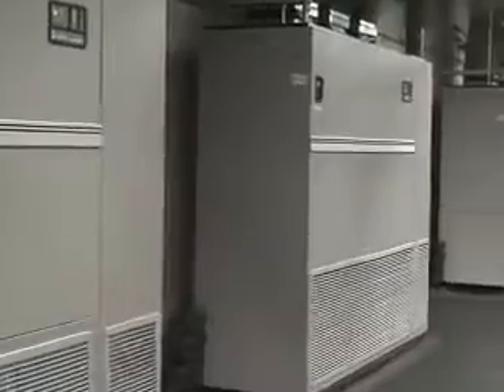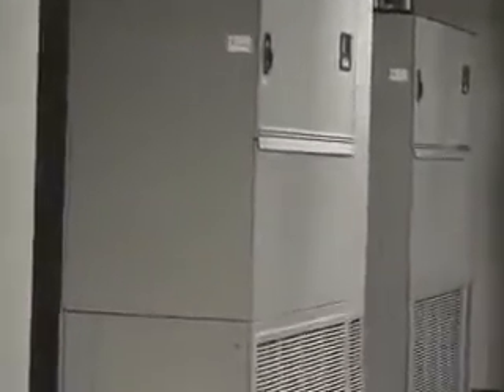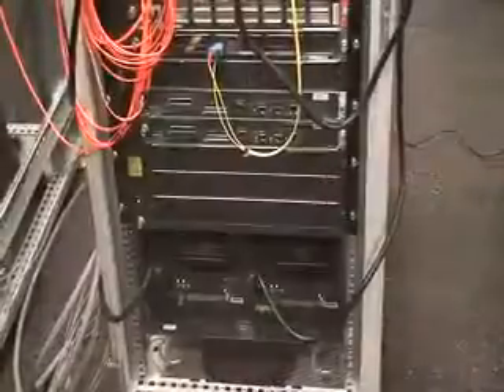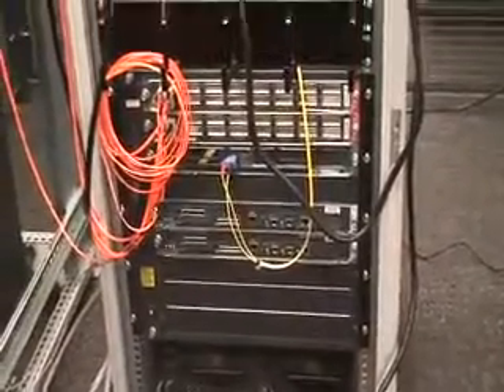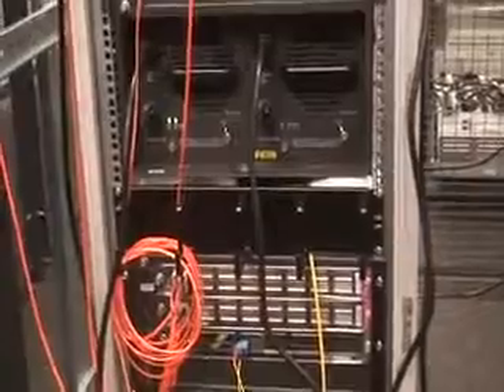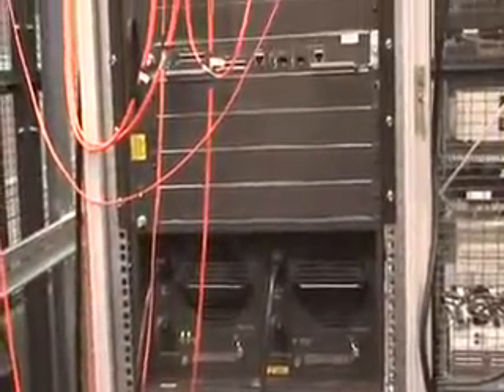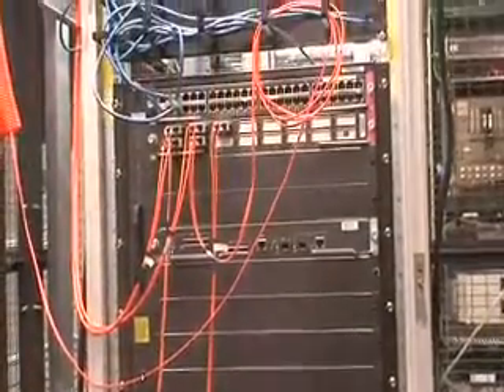Additionally, our electrical and data rooms are cooled by multiple 30-ton Liebert air handling units. Each 30-ton Liebert consists of 2 15-ton compressors, giving multiple layers of redundancy. Both the electrical and data rooms have N+1 air handlers. Our networking systems also feature a high degree of redundancy with both diverse path and diverse entry points from separate upstream carriers and upstream peering to the national internet.